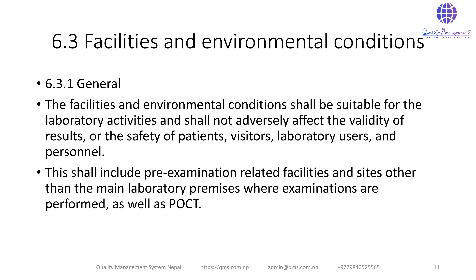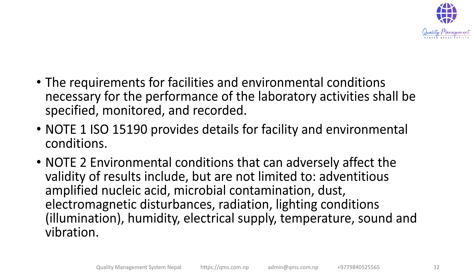6.3 Facilities and Environmental Conditions — 6.3.1 General: The facilities and environmental conditions shall be suitable for the laboratory activities and shall not adversely affect the validity of results or the safety of patients, visitors, laboratory users, and personnel. This includes pre-examination related facilities and sites other than the main laboratory premises where examinations are performed, as well as POCT. The requirements for facilities and environmental conditions shall be specified, monitored, and recorded.